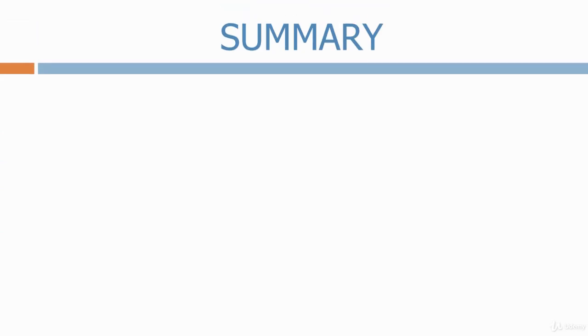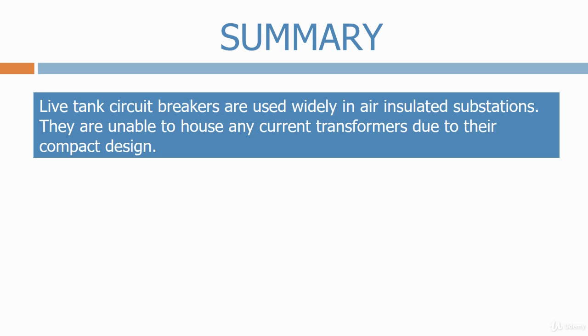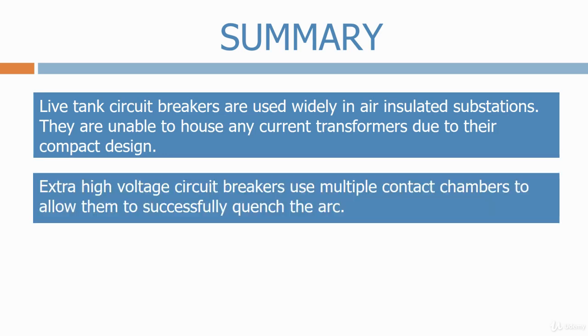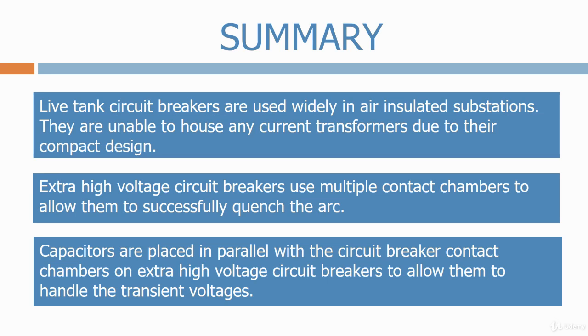Let's summarise what we've learned today. Live tank circuit breakers are used widely in air-insulated substations. They are unable to house any current transformers due to their compact design. Extra high voltage circuit breakers use multiple contact chambers to allow them to successfully quench the arc. Capacitors are placed in parallel with the circuit breaker contact chambers on extra high voltage circuit breakers to allow them to handle the transient voltages.